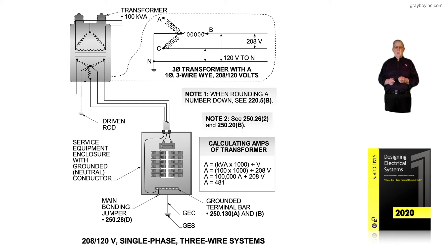Note 2 points out that we would reference 250.26(2) and 250.20B, which illustrates that we'd have two ungrounded conductors with a neutral, and we would ground the grounded conductor or neutral to earth ground in accordance with 250.50, 250.52, and 250.53.